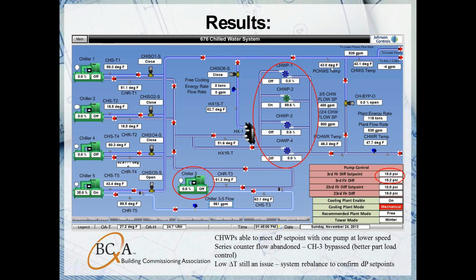You can still see here, though, on this picture that we are experiencing low delta T, and we provided a recommendation to the owner that they get a full chilled water system balancing done to troubleshoot this issue. We were looking at those third floor heat exchangers. Those had a low delta T across them, so potentially this 15-pound differential pressure set point for the third floor heat exchangers is too high and could possibly be lowered.